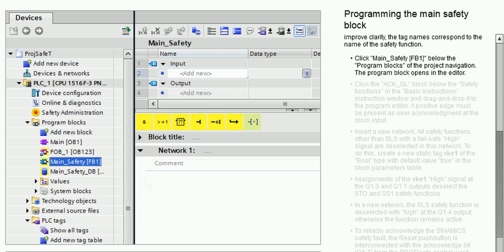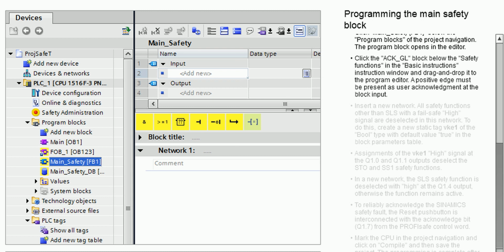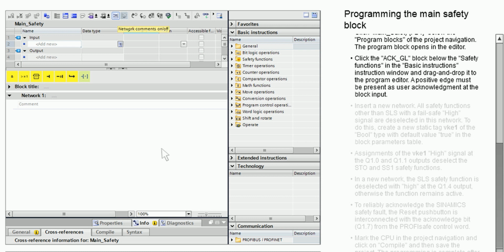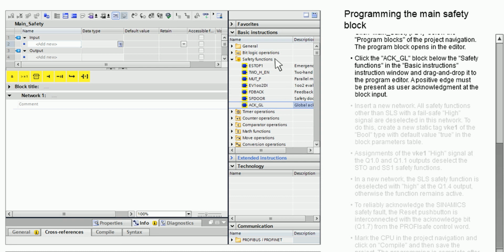Click Main Safety, FB1, below the Program blocks of the project navigation. The program block opens in the editor. Click the ACKGL block below the Safety Functions in the Basic Instructions instruction window and drag and drop it to the program editor. A positive edge must be present as user acknowledgement at the block input.